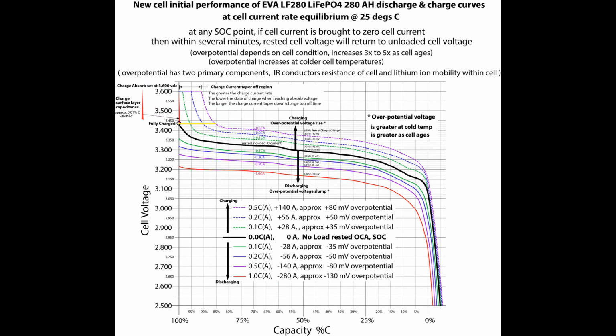I've seen a couple of websites where guys have done it without the BMS. They've basically set it to 28 volts, a little less than the 29.5 volts that would be the maximum for the batteries, giving it a bit of cushion. But you have to be right on top of everything — you need to be there with a multimeter, hour by hour, making sure every cell stays well below 3.65 volts. No cell can ever go above that.